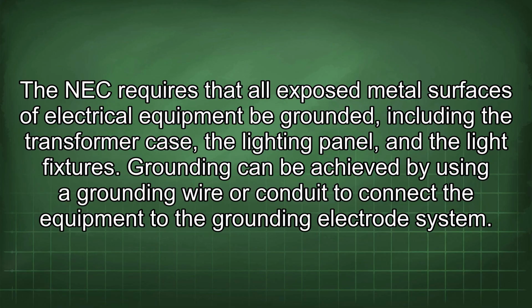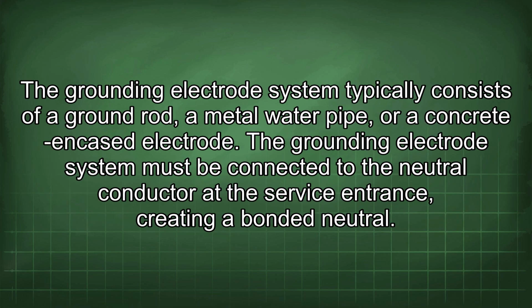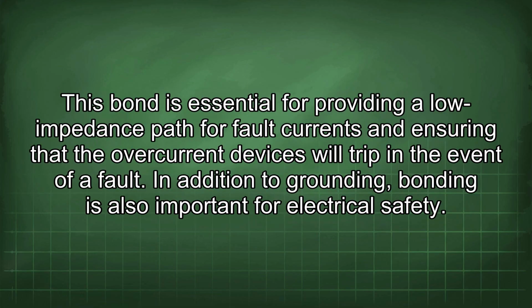Grounding can be achieved by using a grounding wire or conduit to connect the equipment to the grounding electrode system. The grounding electrode system typically consists of a ground rod, a metal water pipe, or a concrete encased electrode. The grounding electrode system must be connected to the neutral conductor at the service entrance, creating a bonded neutral. This bond is essential for providing a low impedance path for fault currents and ensuring that the overcurrent devices will trip in the event of a fault.